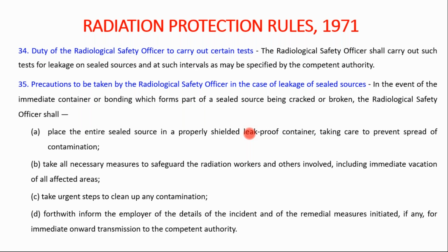Take all necessary measures to safeguard the radiation workers and others involved, including immediate evacuation of all the affected areas. Then take urgent steps to clean up any contamination. Forthwith, inform the employer of the details of the incident and the remedial measures initiated, if any, for immediate onward transmission to the competent authority.